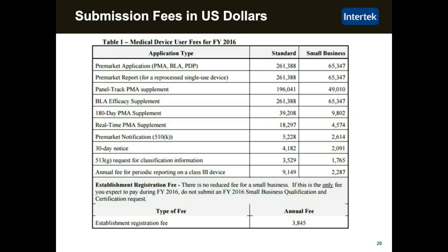This slide provides an overview of the 2016 fees, and just a quick comment that they do have two sets of requirements. One is for what they consider a standard business, and that would be any medical device manufacturer with sales in the U.S. over $100 million. And then you have a small business, and that would be a medical device manufacturer with sales under $100 million. And you can see there's a significant difference in the cost of a PMA, $260,000 versus $65,000. And the differences go all the way down to all sorts of different aspects of the PMA as well as 510K. There are annual registration fees, but that's fixed and doesn't differentiate between the size of the organization.